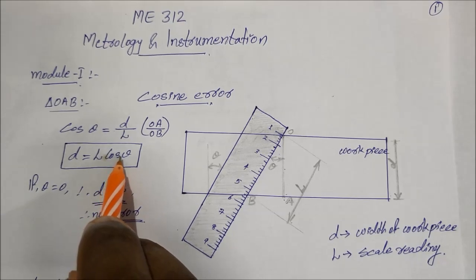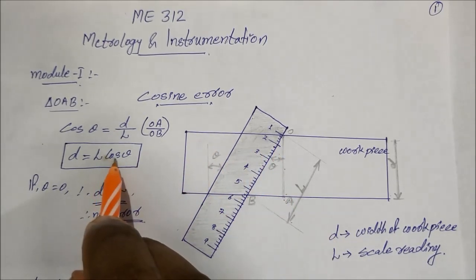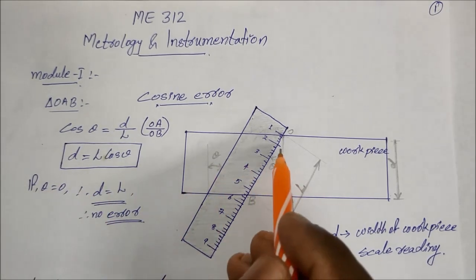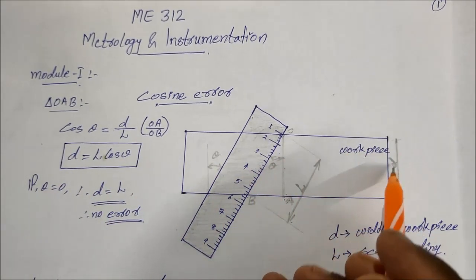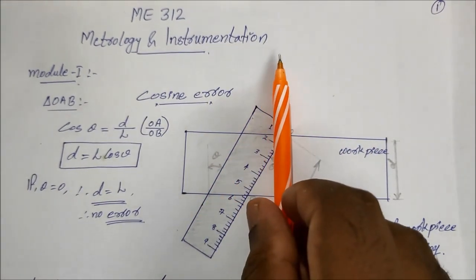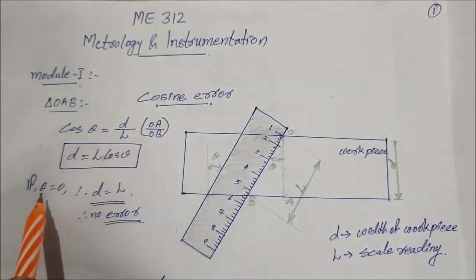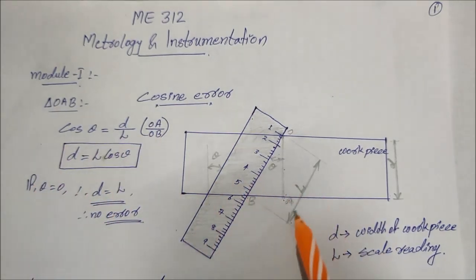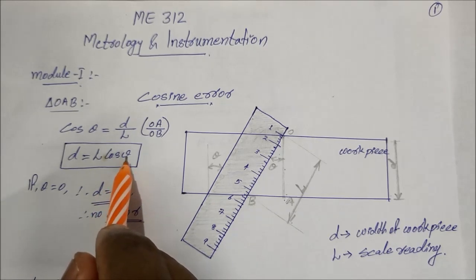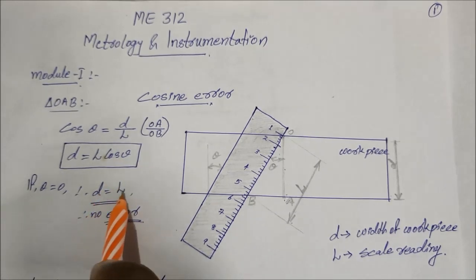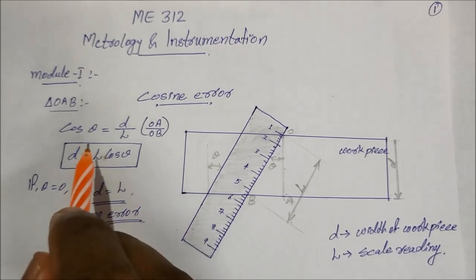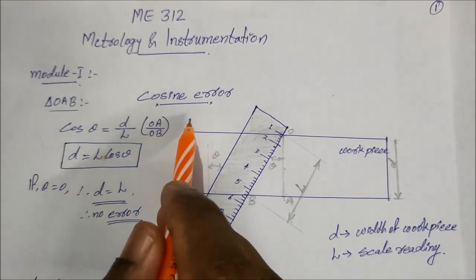If cos theta is not corresponding, errors are created. For example, if theta equals 0, that means the workpiece and the measuring scale are parallel, so theta is 0. The scale reading value is L. Cos 0 equals 1, that means d equals L. So no error is created. This error is called cosine error.